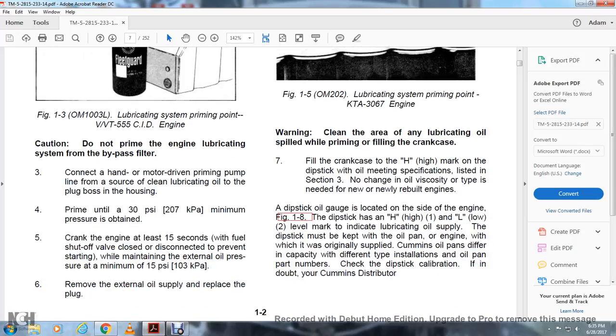Caution: do not prime the engine lubricating system from the bypass filter. Connect a hand or motor-driven priming pump line to the source of clean lubricating oil at the plug boss in the housing. Prime until the 30 psi minimum pressure is obtained. Crank the engine at least 15 seconds with the fuel shut-off valve closed and disconnected to prevent starting, while maintaining the external oil pressure at a minimum of 15 psi. Remove the external oil supply.